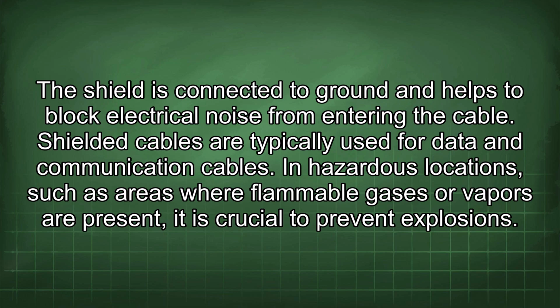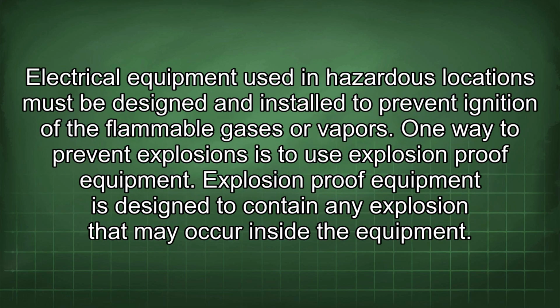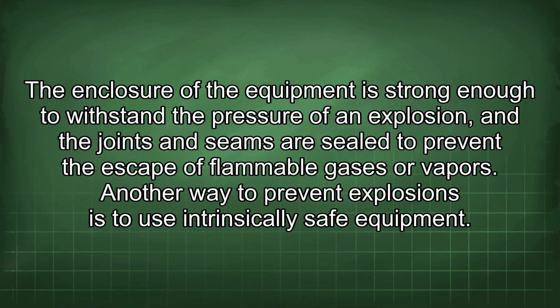In hazardous locations, such as areas where flammable gases or vapors are present, it is crucial to prevent explosions. The electrical equipment used in hazardous locations must be designed and installed to prevent ignition of the flammable gases or vapors. One way to prevent explosions is to use explosion-proof equipment. Explosion-proof equipment is designed to contain any explosion that may occur inside the equipment. The enclosure of the equipment is strong enough to withstand the pressure of an explosion, and the joints and seams are sealed to prevent the escape of flammable gases or vapors.